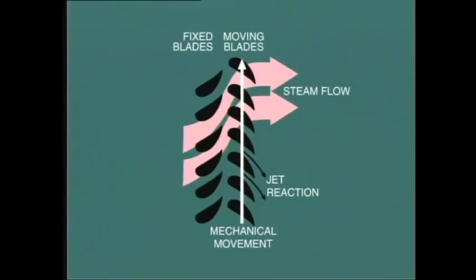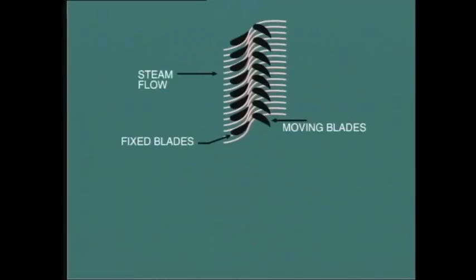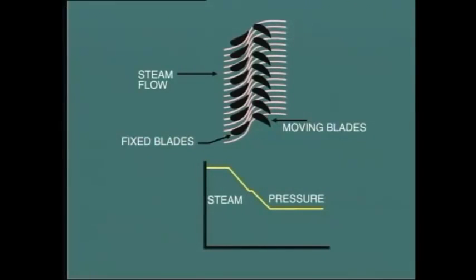Now let's move on to look at the characteristics of reaction-type blading. In this case, the mechanical force on the blade is caused by reaction as the jet of steam exits from the blade. This is the same concept as a jet engine. With this type of blading, the moving blades are shaped in the same manner as the fixed blade, that is, in the profile of a curved nozzle. This causes the steam pressure to fall as it passes through the moving blade, resulting in an expansion of the steam and an increase in its velocity relative to the blade, causing a powerful jet action.